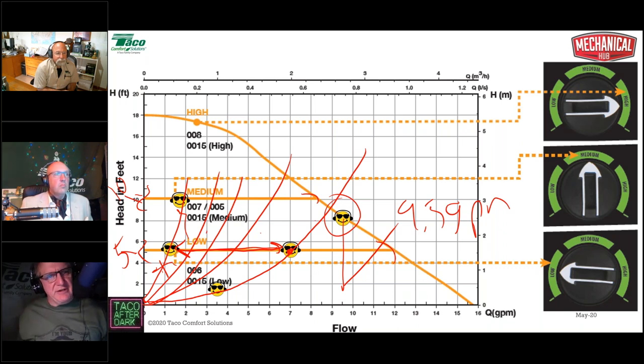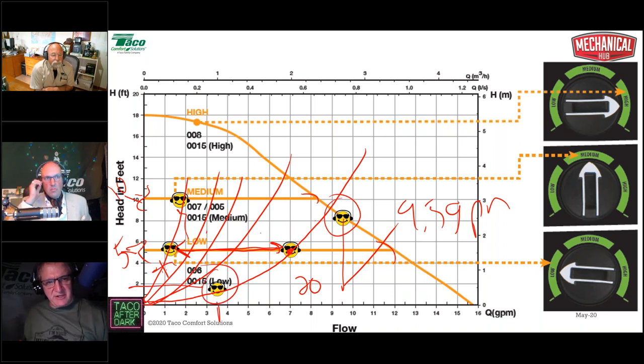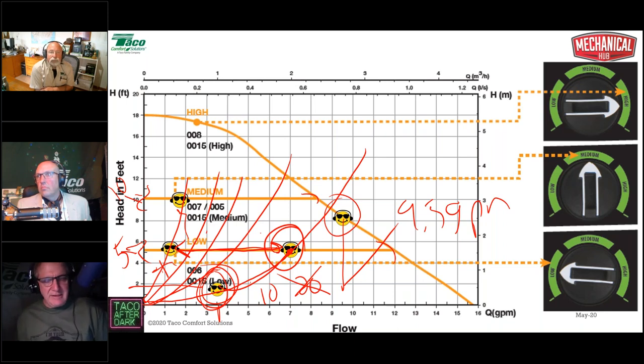In terms of addressing the incredible shrinking delta T here, we haven't done very much, all right? We really haven't. If we go to 5 foot of head, at least we know under design conditions, it's going to be pretty close to 20. But as it gets warmer and warmer out, the delta T is going to get smaller and smaller. In fact, here's 3.5 gallons a minute, a little over a foot of head, that's 50% load. I want it to work here, it's going to work there. Now my delta T won't be 20, my delta T will be 10. That's just the way it works, okay? Not bad, it's not the same as delta T, but it's certainly not bad.